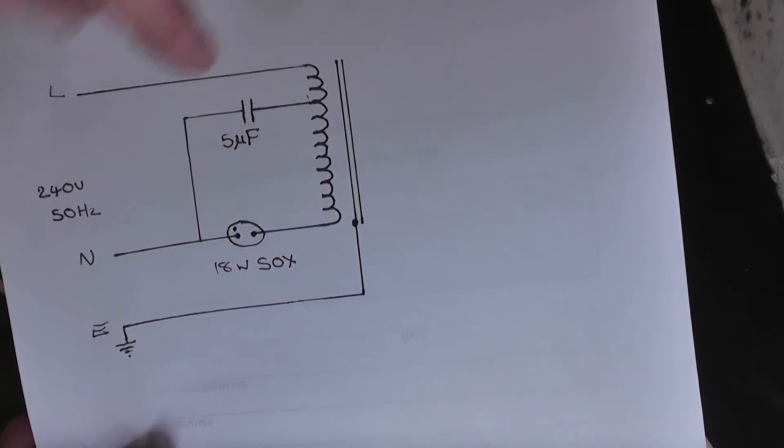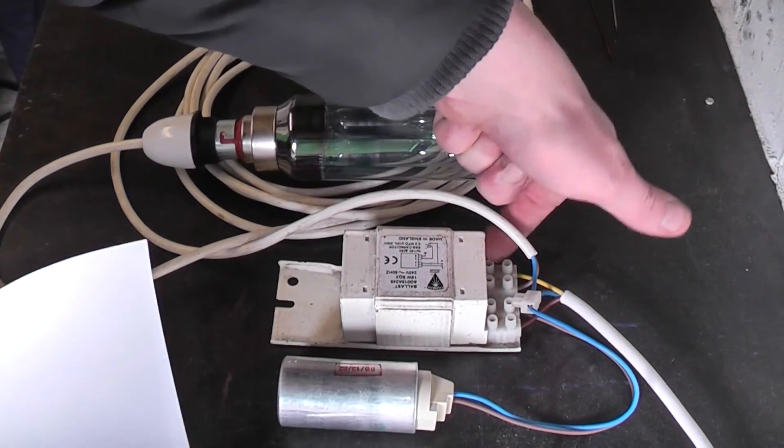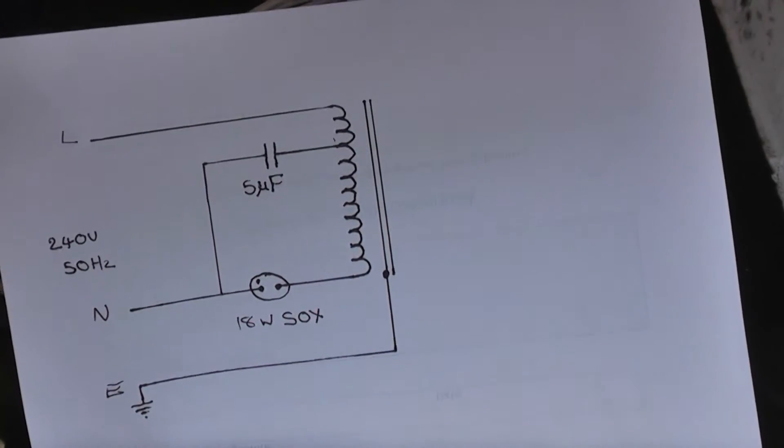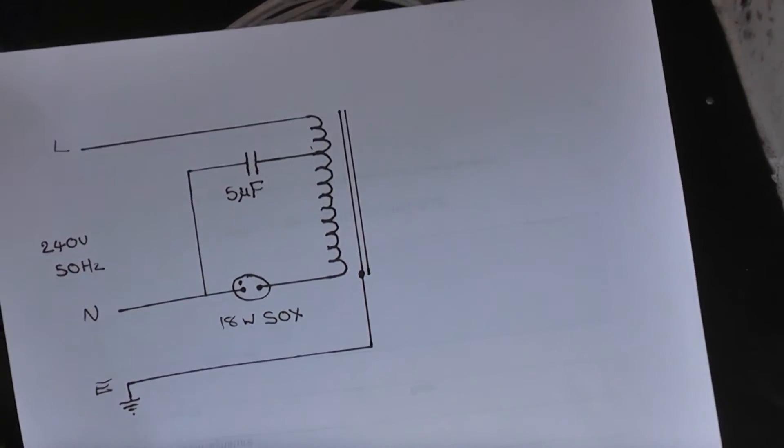There's the lamp, you've got your live coming in across there, neutral earth which is connected to the ballast casing. When the lamps first switched on, the lamp is physically connected to the ballast but electrically it's not until the gas ionises.